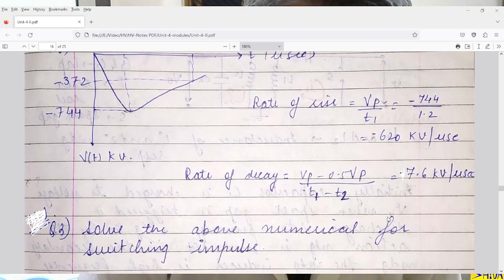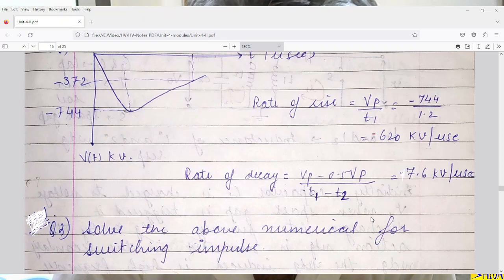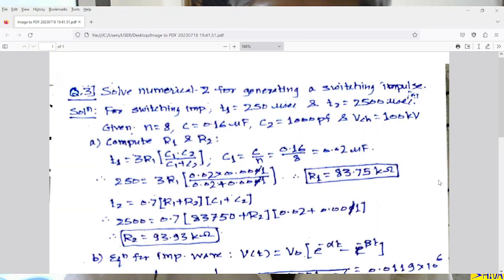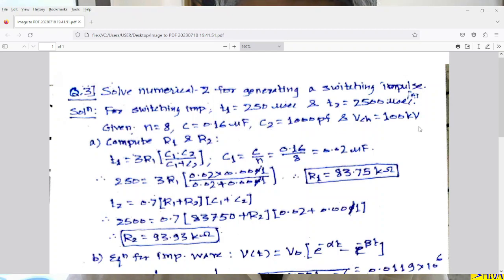Now we solve the same numerical for switching impulse, computing all values for switching impulse. For switching impulse, T1 (rise time) = 250 microseconds and T2 (tail time) = 2500 microseconds. So all the calculations will change. Given: N = 8, C = 0.16 microfarad, C2 = 1000 picofarad, charging voltage = 100 kV. First compute R1 and R2. C1 = C/N = 0.16/8 = 0.02 microfarad. In the formula for T1, taking R1 in ohms and C1, C2 in microfarads, T1 comes directly in microseconds.